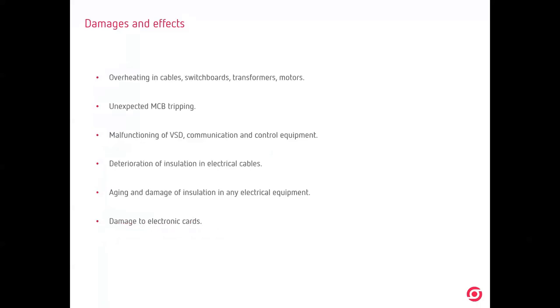Overheating of the cables or the switchboards, transformers, and motors, okay? Having more current through the cables. If you have more current in the cables, you can have unexpected trippings of the MCBs, because you are increasing the current, okay? If you have variable speed drives, they cannot work properly because you are adding different signals in high frequency that can interrupt the communications and can make resets in the control devices.